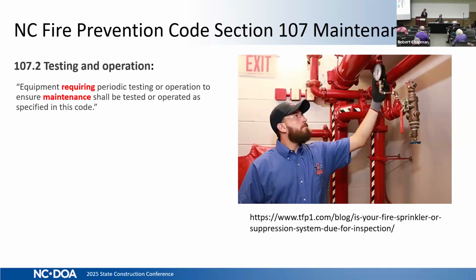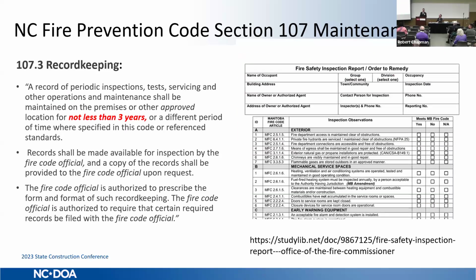All right. And then as we continue on with the North Carolina Fire Prevention Code, it talks about testing that has to be done as well as maintenance. Certain systems in our facilities require testing, so that we make sure they're going to operate when they're actually needed. And not only do they have to do the testing and the maintenance, but they also have to follow up with recording the fact that they've done those. So we see some standard logs, and our maintenance folks, unfortunately, don't have enough things to do on their plate. They also have to make sure they do the record keeping. They have to keep these records for not less than 3 years. Some codes make you keep those a little bit longer, so we have to follow those. And then they have to be able to be presented upon demand to the authority having jurisdiction.